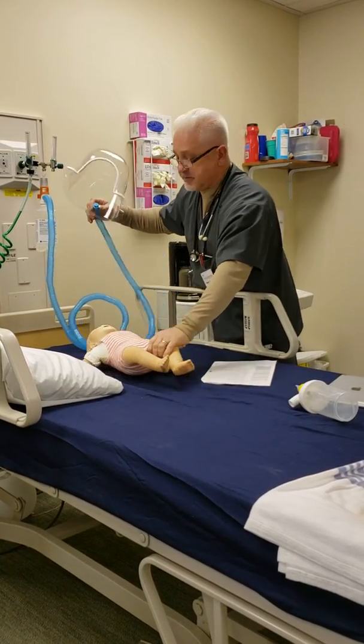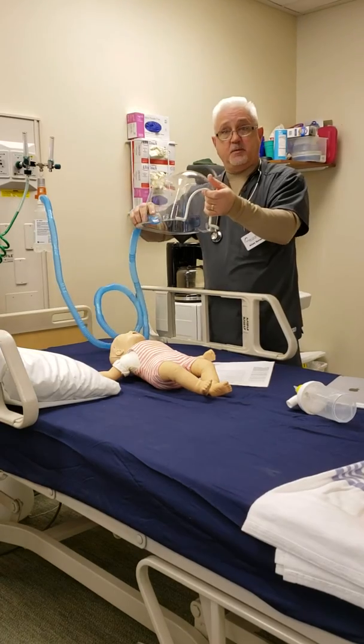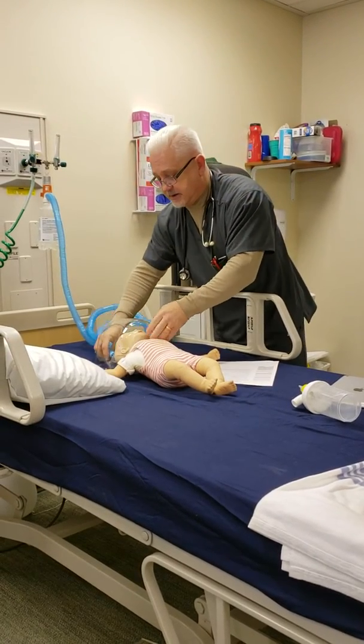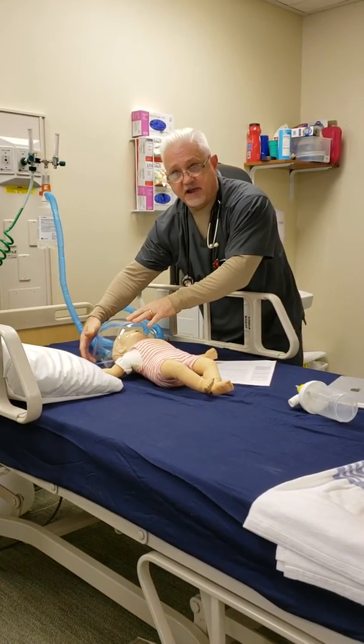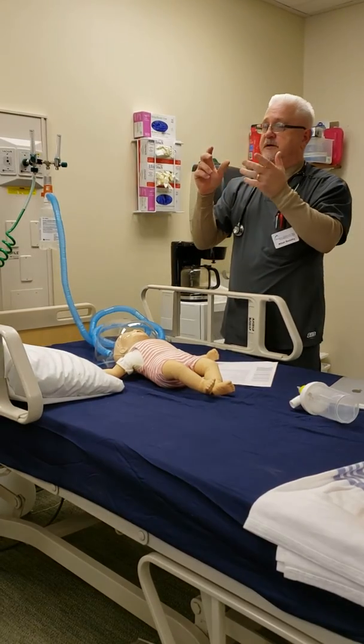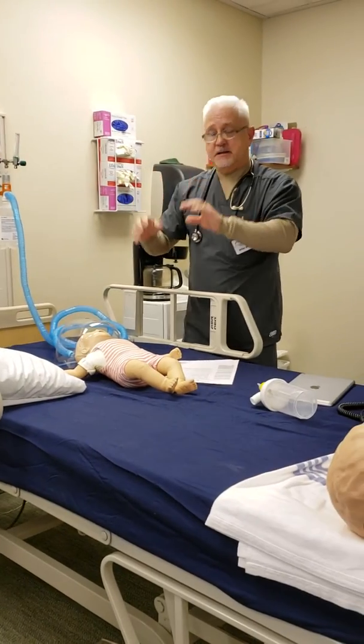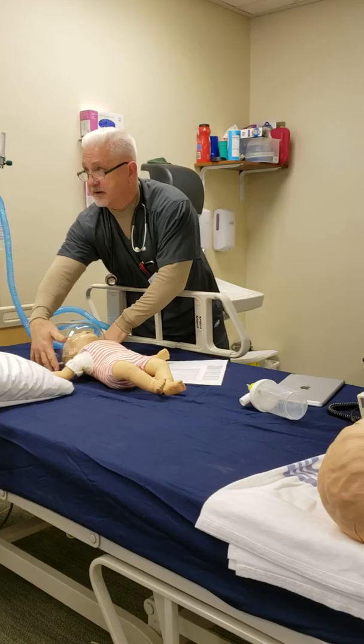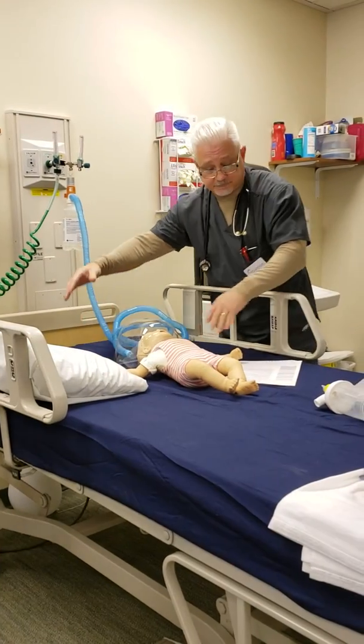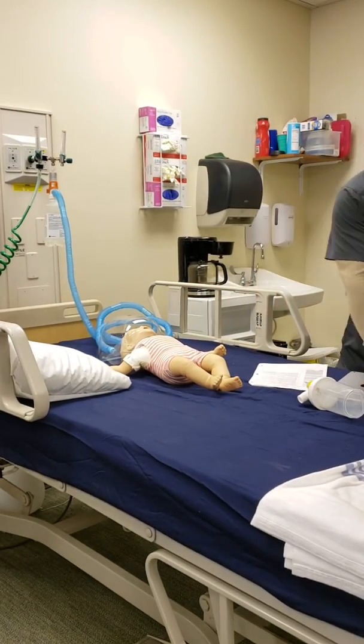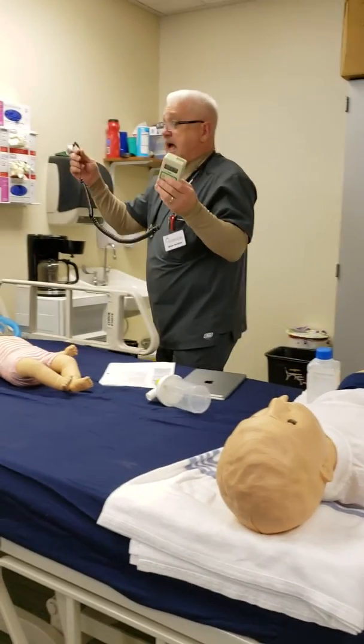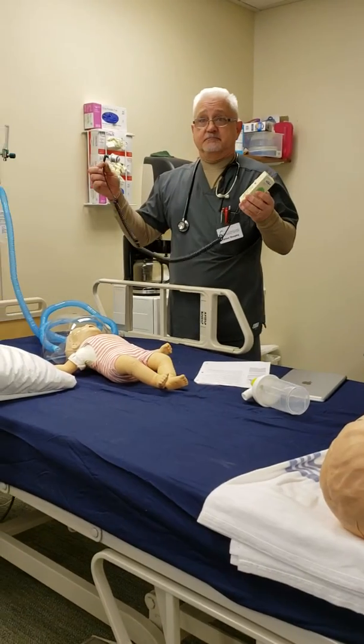I'm going to set the temperature. My temperature probe will be down closest to the patient. There's a flexible metal plastic covered bar that would sit over the top of the hood to keep the hood down. Then I would also have my O2 analyzer. And there's two different trains of thought here, okay?